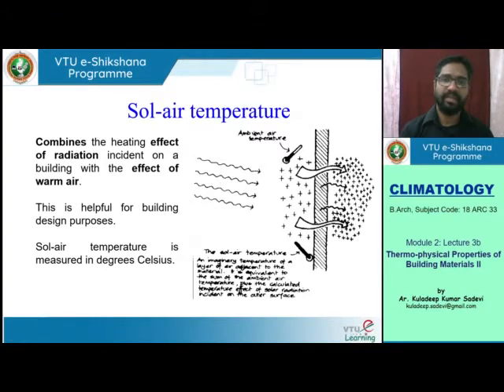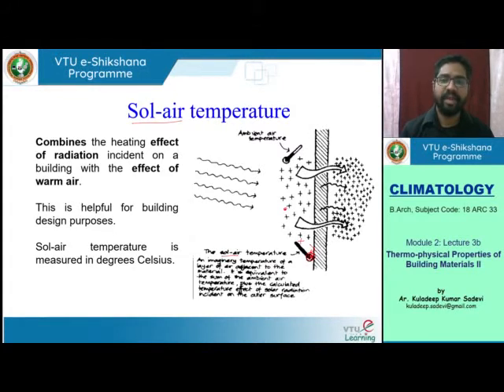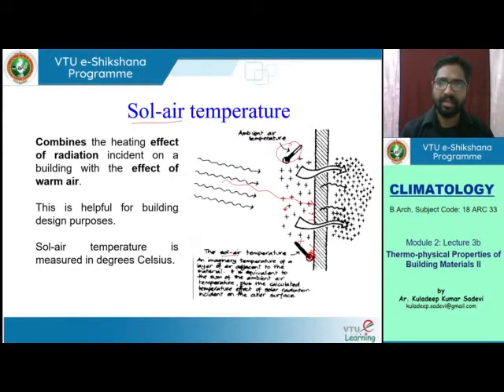The first concept is solar air temperature. Solar air temperature is not just the ambient air temperature. If you take a temperature reading of the air outside the wall you get a certain reading, but the temperature of the air adjacent to that outdoor wall will have the impact of the ambient air temperature plus the impact of the radiation that adds to the temperature of this air. So solar air temperature is an imaginary temperature of a layer of air adjacent to the surface — it is the sum of the ambient air temperature plus the calculated temperature effect of solar radiation.